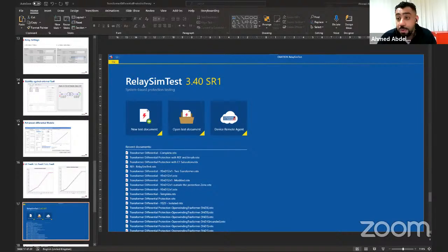And what my CMC is going to do is, let me clear it. Afterward, you will see that I can have different bias values, and the CMC will inject this, and it will go here in this area, simulate a fault, the trip, and it will go to this area and simulate a fault that doesn't trip. So it will detect there is a line here. Then it will minimize the step of the movement till it finds the intersection between the search line and the characteristic.